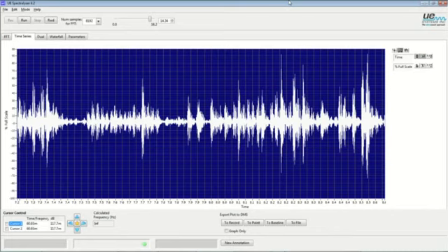Okay, great. Another question, is electrical discharge voltage dependent? If the question's being asked in the context of do you need a certain potential or a certain voltage level to experience discharges, the answer would be no. Our experiences have shown down to 120 volts AC, we have identified accurately tracking events taking place.